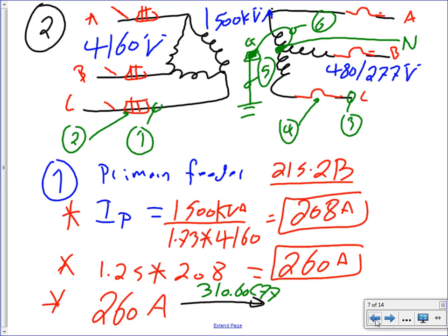No, I'm saying because you said if it's over 600 volts, we're responsible for it. If your service coming to your building is 600 volt or less, meaning Excel is giving you a 480 transformer outside on the secondary side, then you don't worry about the primary side. They bring the primary side. If your service is 13.8, meaning these cables are actually your service coming to your building here, then you're responsible for installing them. Not Excel's stuff. This question is why. Yeah, why?